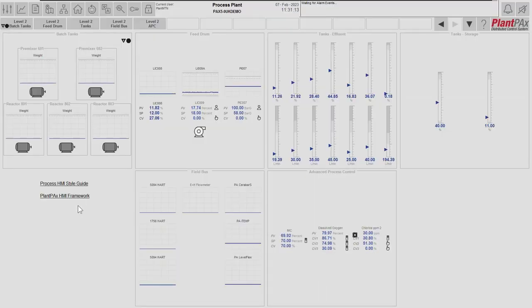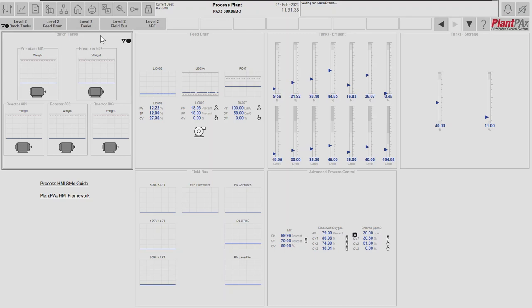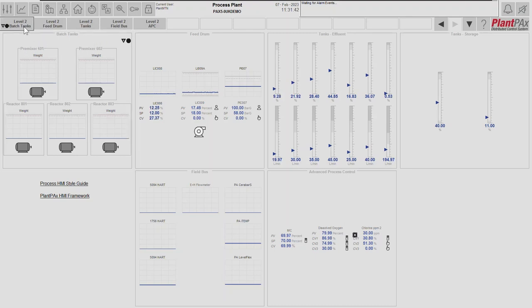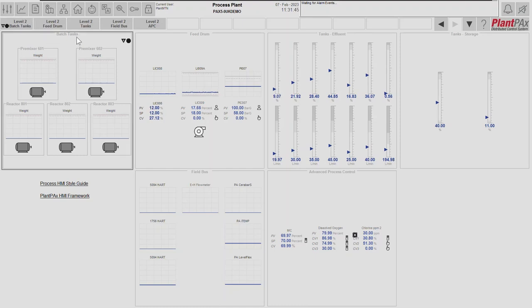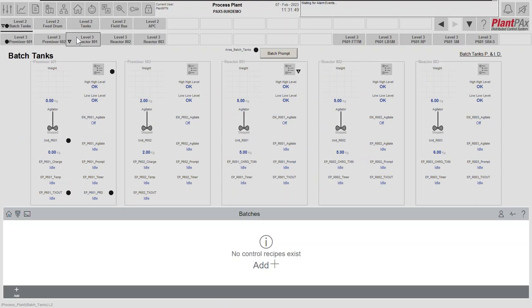Let's look at this in action. Here we have a demonstration system where we can see status information being indicated using the Organization, Ownership and Arbitration framework. In the top level menu we can see that in the level 2 batch tank area we have some issues - a spanner symbol and a black dot - and that's been indicated in the batch tank area as well. From the HMI, the user can navigate into the batch tank area either by using the menu button or clicking directly on it to be taken to the level 2 display, where the issue is highlighted in premixer 601.